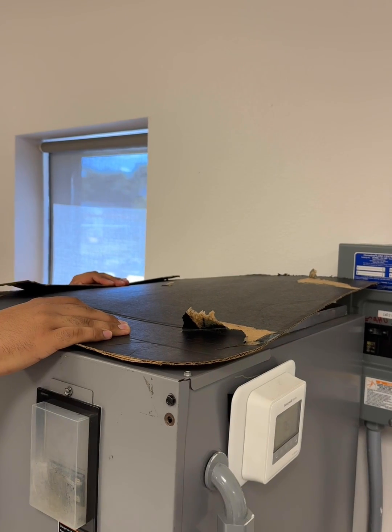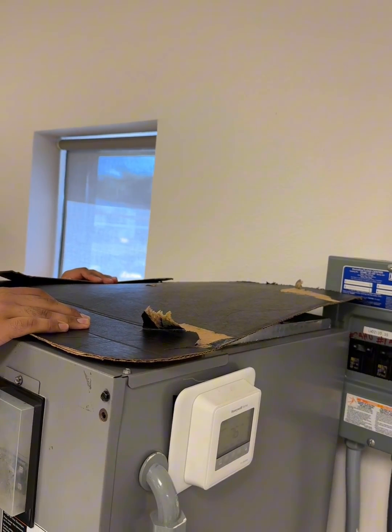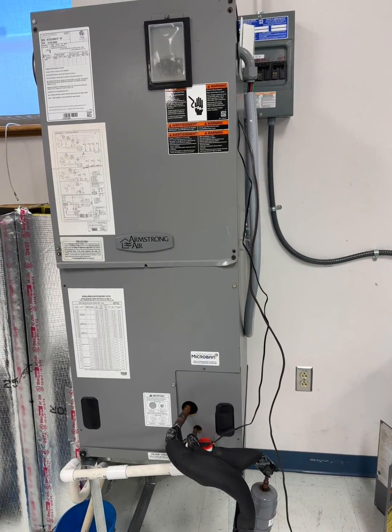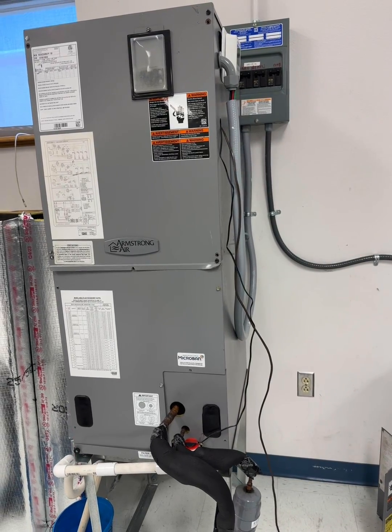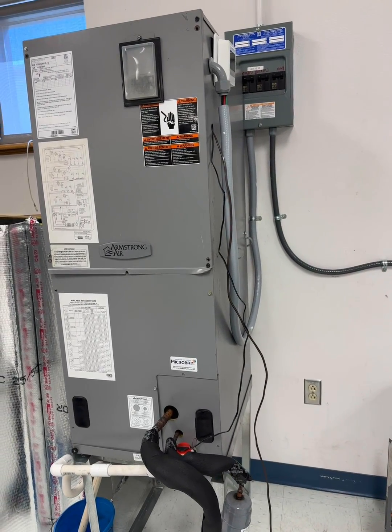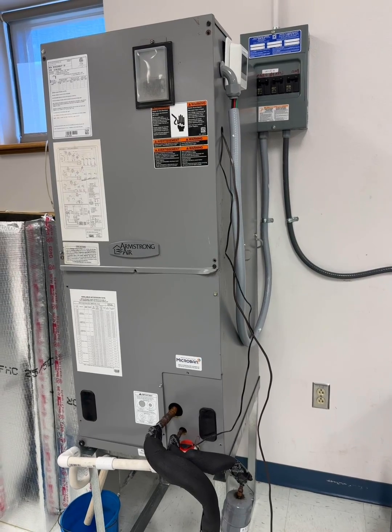A restriction in the air handler could cause inefficient cooling and could cause the blower motor to fail, especially an ECM motor, which increases its speed due to the restriction, trying to push the air out.